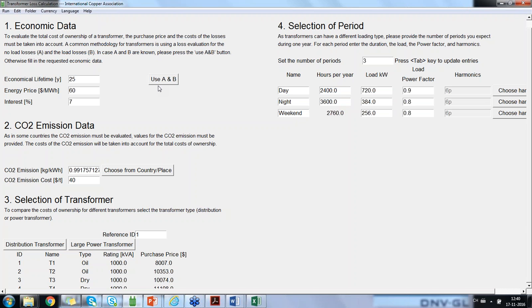We have another question. How does the K factor affect harmonic losses in transformers? Excellent question. The K factor is, I think, more used in the US than within Europe. In the US, they have another way of dealing with harmonics and specification of transformers. We didn't look at the K factor within this presentation, but in the past we have made a report on that, including all the theoretical background, which is also used in this tooling. I will be happy to provide that report to you.